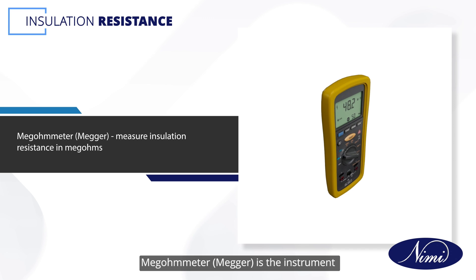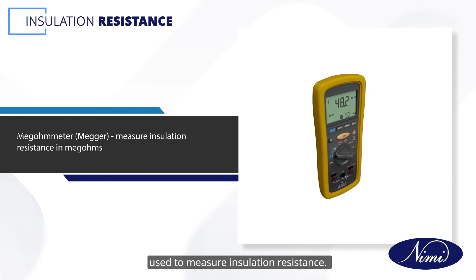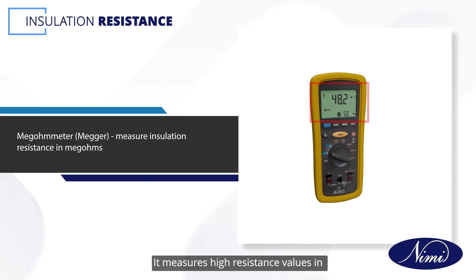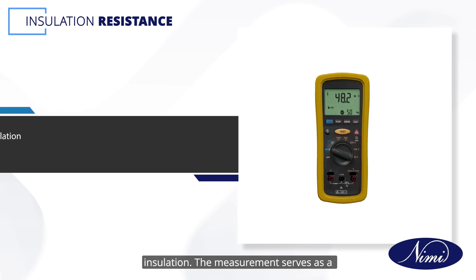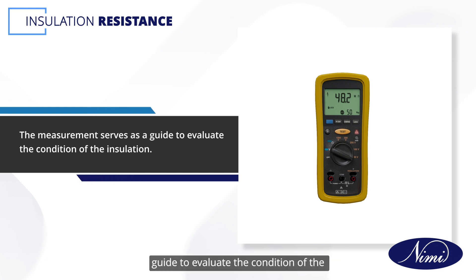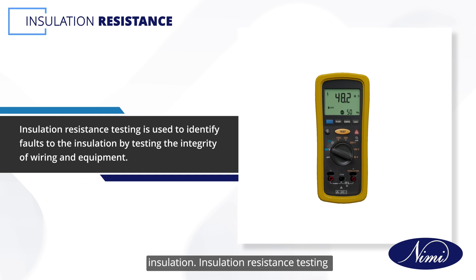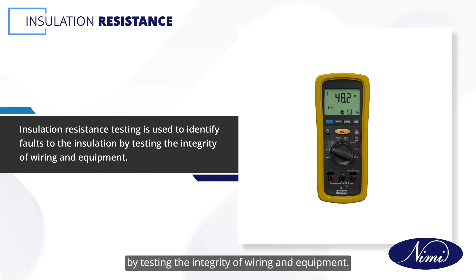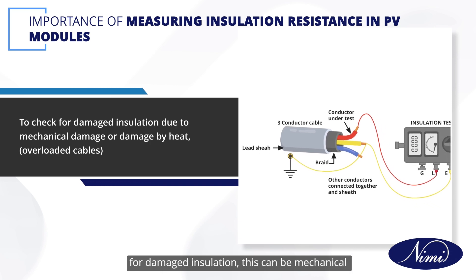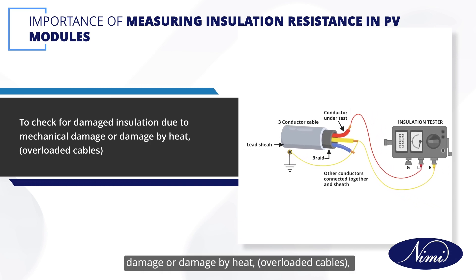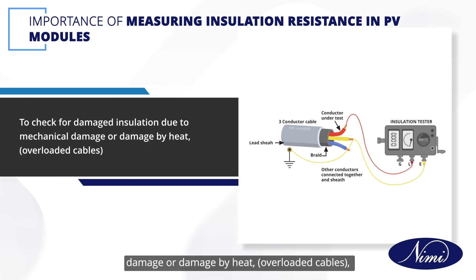The Megohmmeter (Megger) is the instrument used to measure insulation resistance. It measures high resistance values in megohms without causing damage to the insulation. The measurement serves as a guide to evaluate the condition of the insulation. Insulation resistance testing is used to identify faults to the insulation by testing the integrity of wiring and equipment. The purpose of the IR test is to check for damaged insulation, which can be mechanical damage or damage by heat or overloaded cables.